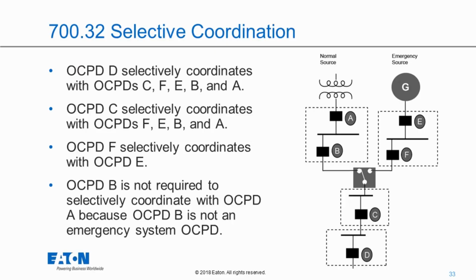So what we clarified here was that the emergency system overcurrent devices must selectively coordinate with all supply side overcurrent devices, whether that is a normal supply side or an emergency supply side device. If I look at device D, if there is a fault on the load side of device D, it must operate. However, devices C, F, E, B, and A are required to not operate. If we look at a fault on the load side of device C, it must clear that fault, and devices F, E, B, and A must not open. If we look at a fault on the load side of device F, device F must clear and device E must not open.